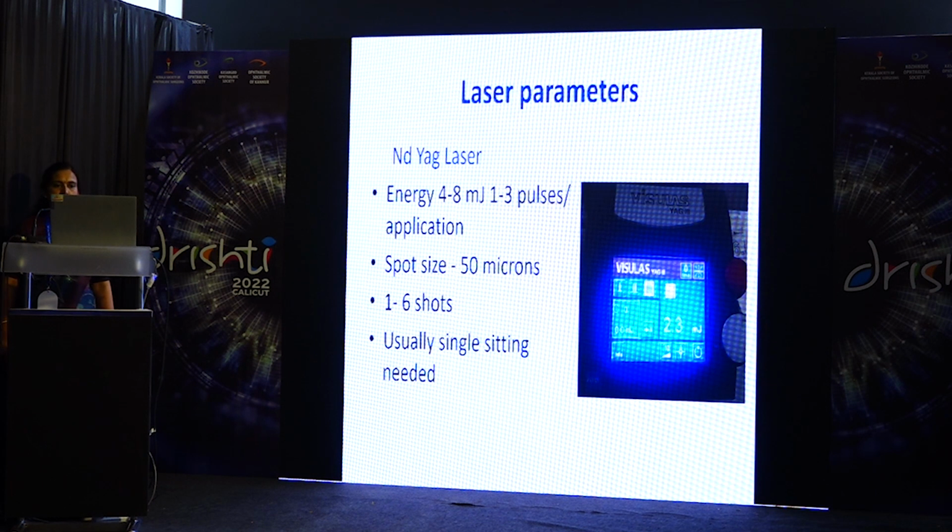Coming to laser parameters, it is fixed for a particular machine, and the usual energy range is 4 to 8 millijoules, 1 to 3 pulses per application, and the spot size is 50 microns, 1 to 6 shots, and in most of the cases, a single sitting is needed.